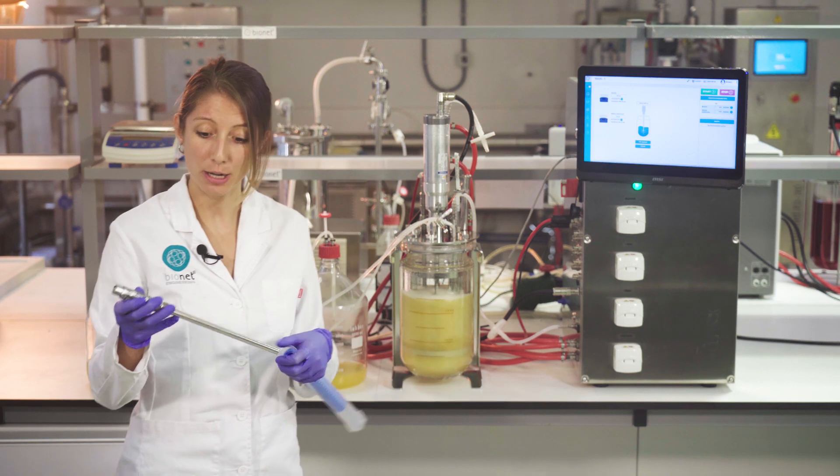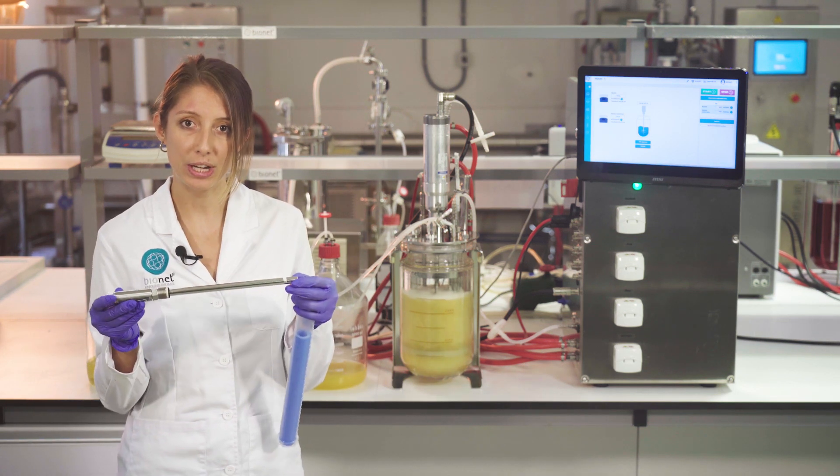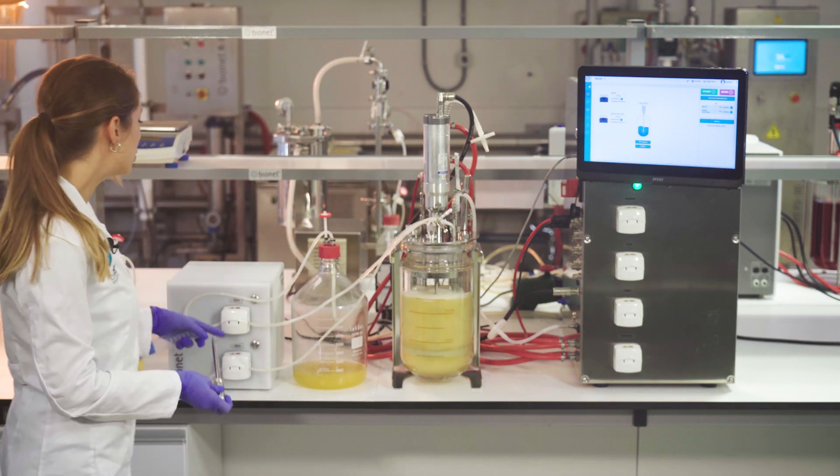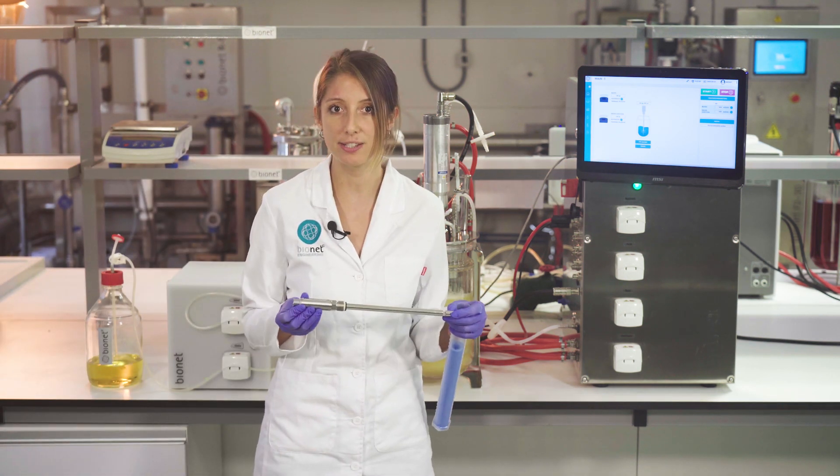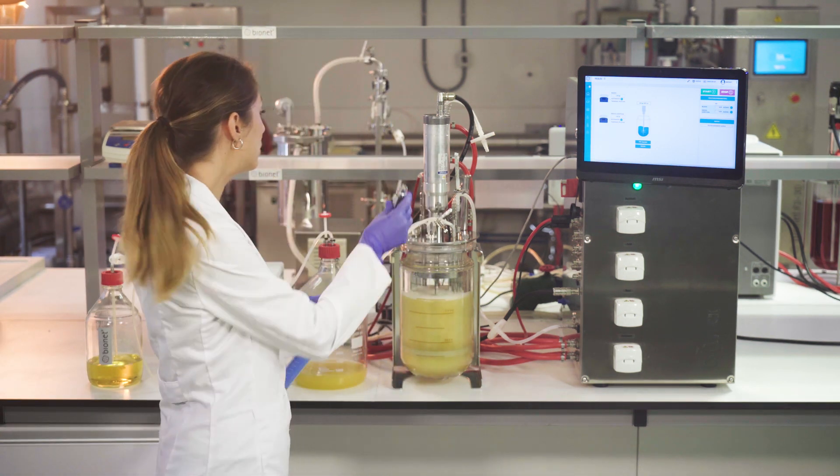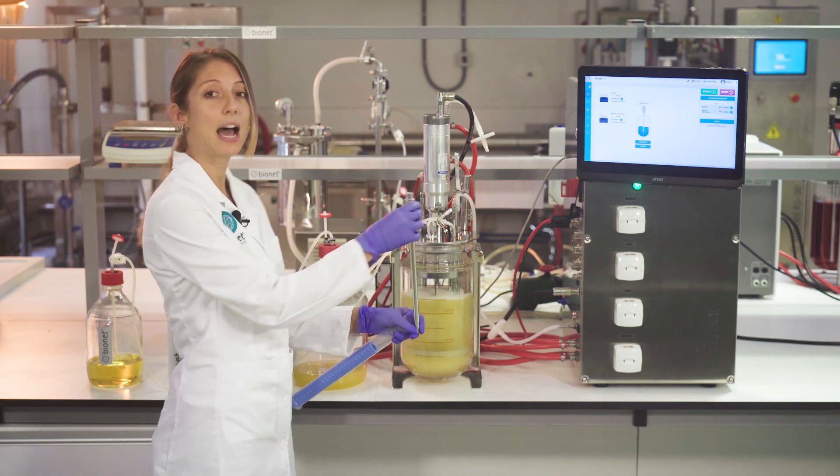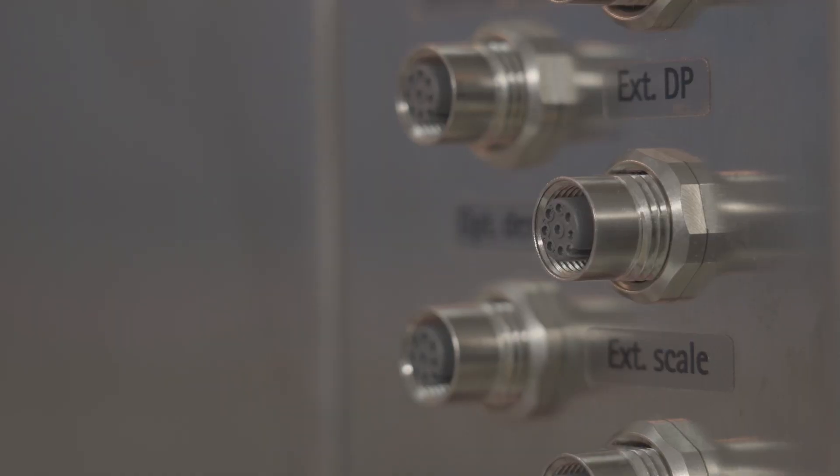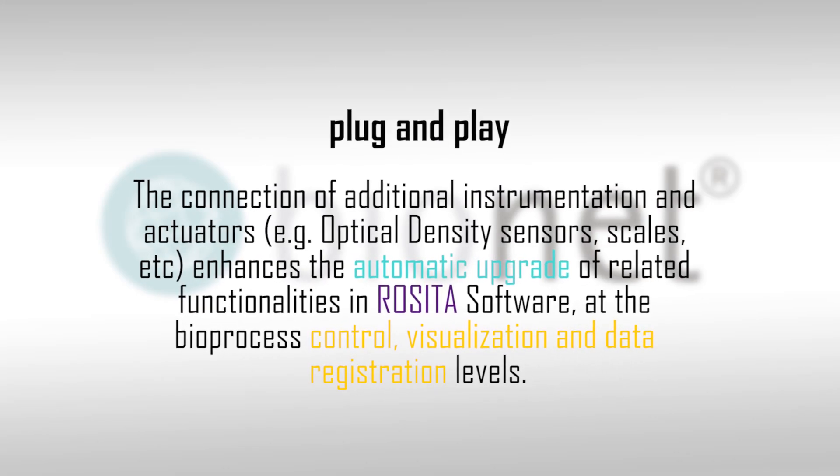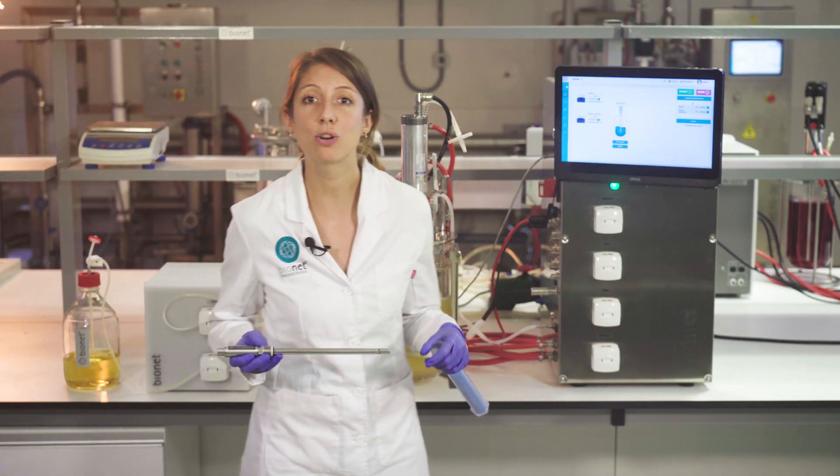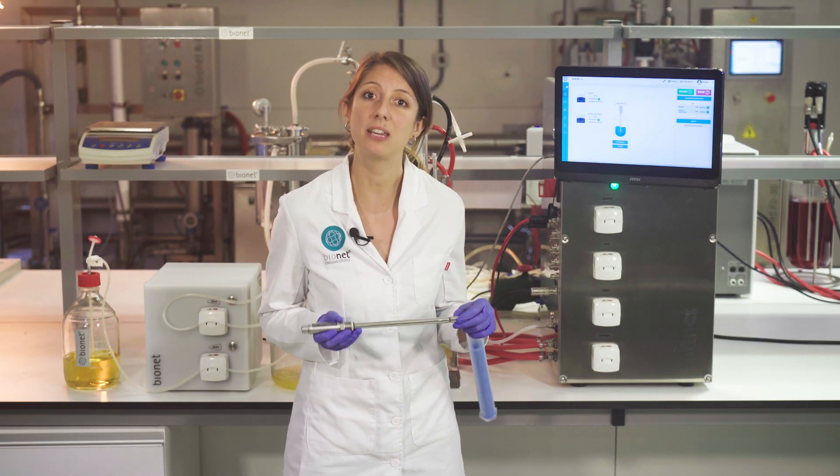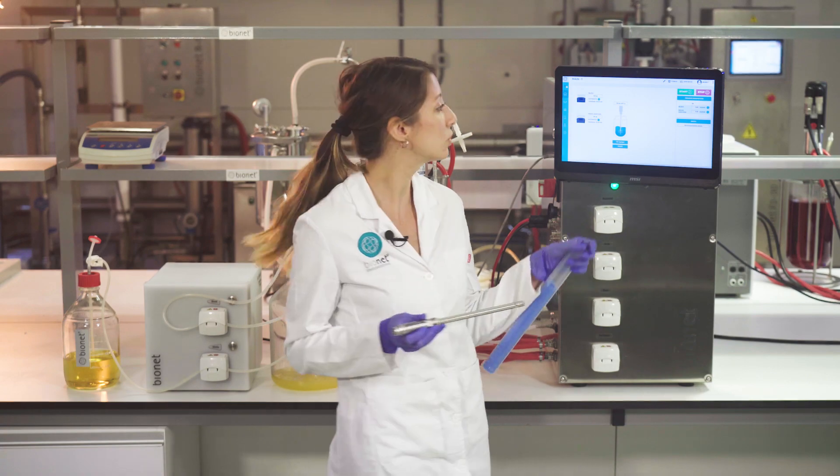For example, if you had an optical density sensor like this one here, the addition and withdrawal pumps could both be configured to respond to the measurements of this sensor that would be introduced into the vessel through the ports and connected to the VCU following the plug-and-play concept. This process is called TurbidoStat and can also be easily programmed with Bionet software modules.